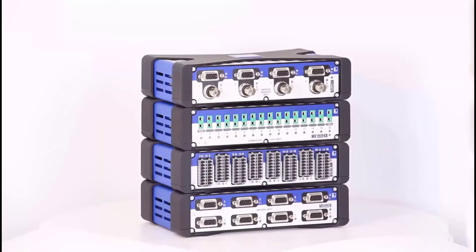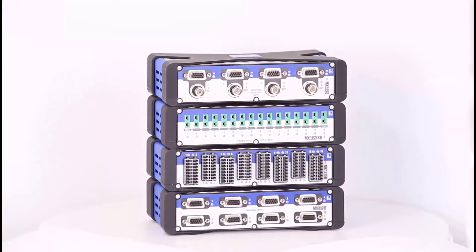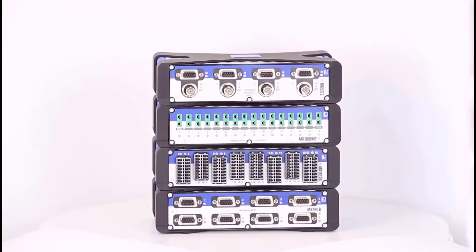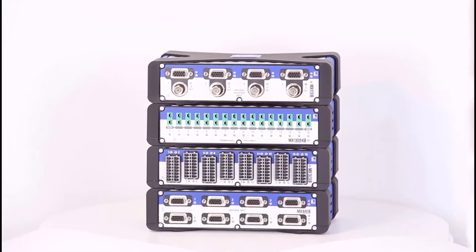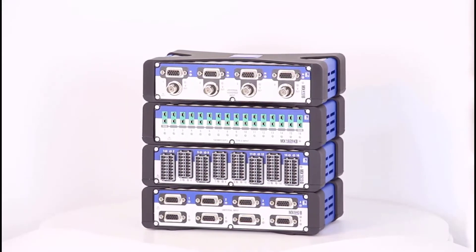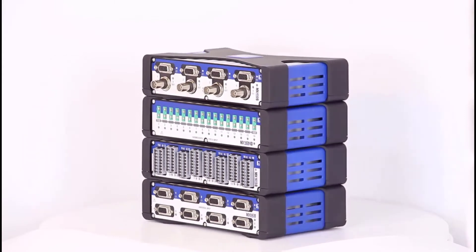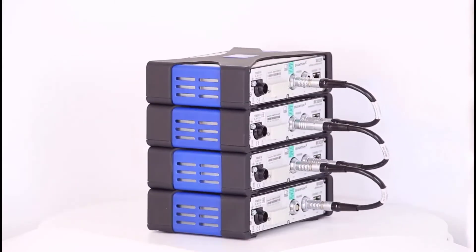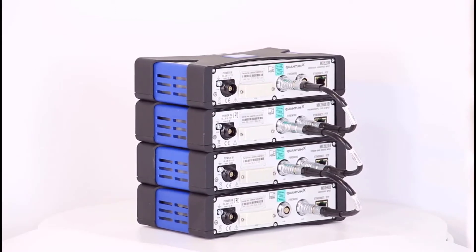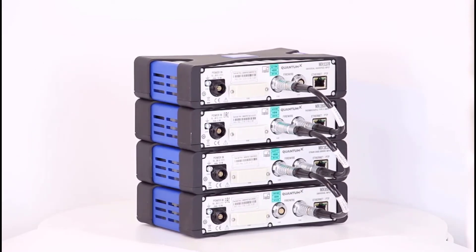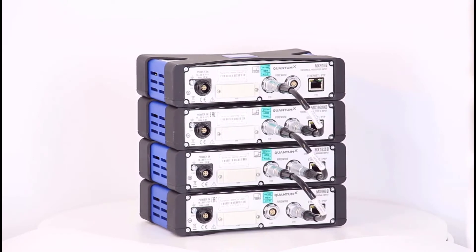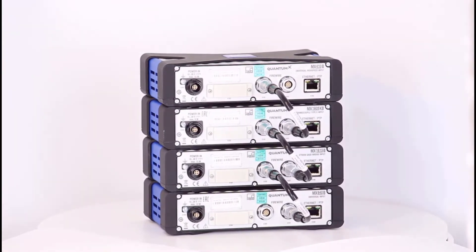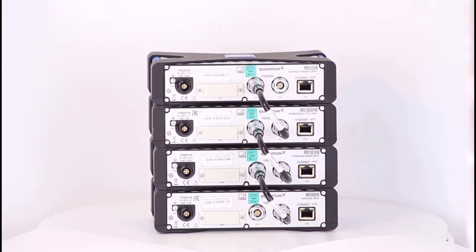To ensure that the modules record their measured values synchronously, I'll use firewire synchronization. Catman and QuantumX alternatively support further synchronization mechanisms such as PTP or NTP. In my project, the firewire synchronization is a good choice. The firewire interfaces of the modules are cross-connected. The firewire cables are available in different lengths and designs. I use short cables here.